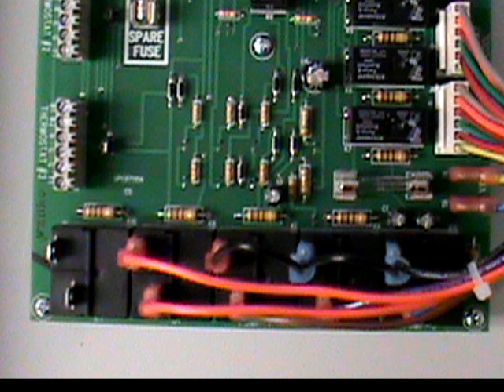An added feature of the control module is that when the master thermostat is in one mode while the other zones are in another, the zones opposite the master zone cannot overheat or overcool the space. In other words, if the master thermostat is set to the cooling mode and one of the other thermostats calls for heating, the pump that serves that zone will not energize, but the fan will be allowed to come on. For applications that require more radiant floor zones, the B1 relay is energized during heating mode and provides a dry contact that can be used to power additional radiant floor zones through a single or multi-pump relay.